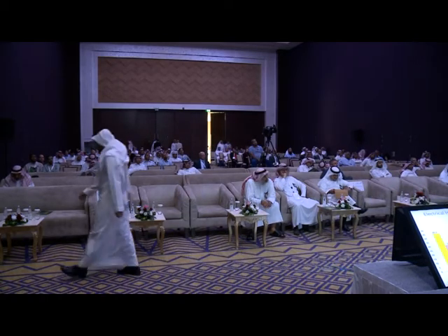Now, my day job is actually doing network analysis and power system analysis and determining correct grading and arc flash energy levels. And let me tell you, there are very few. There's probably only about 5% of the installations that I work with that are more than 80 calories per centimeter squared. So a simple 500 volt glove or 1000 volt glove, which is a class 0 glove, with a thin leather overprotector can offer you 80 calories per centimeter squared. There's no reason why we should not protect ourselves from shock and arc flash. Interestingly enough, the same mechanism that causes electrical shock also causes an electrical arc flash.